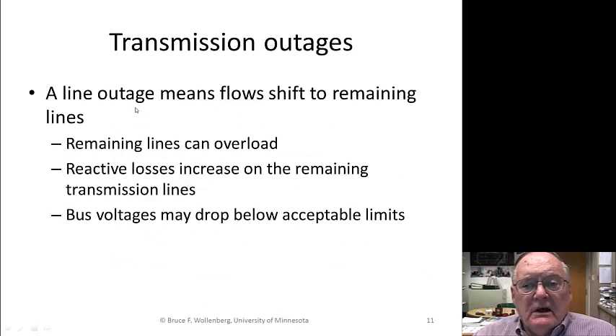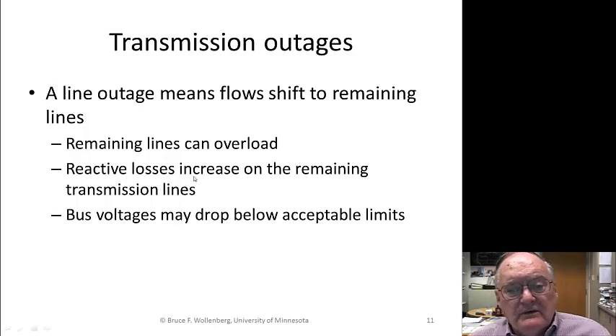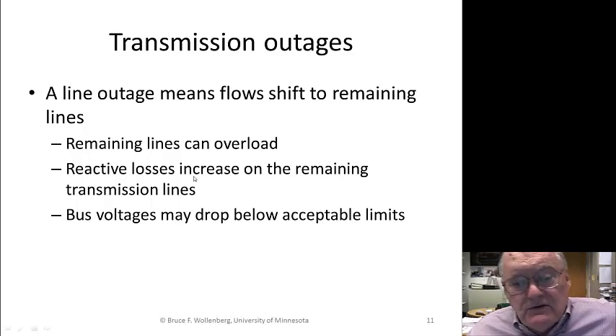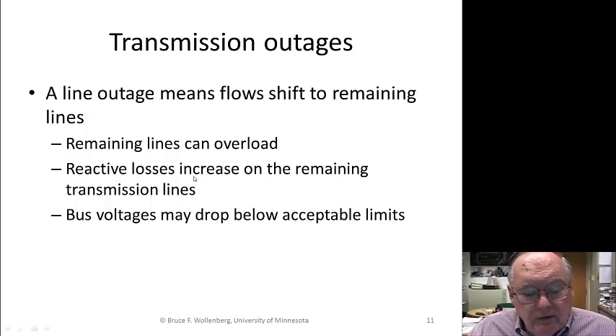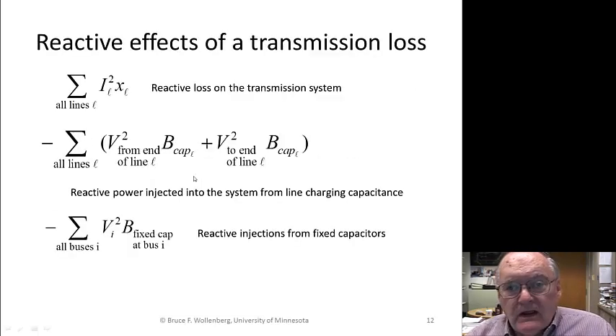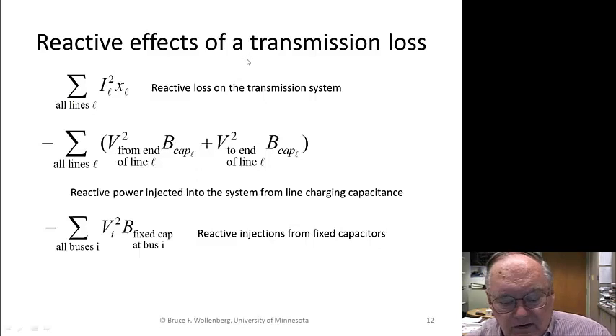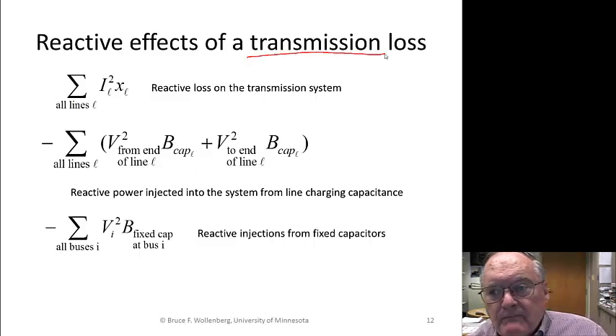Transmission outages. A line outage means flows shift to remaining lines. The remaining lines can overload. The reactive losses can increase on the remaining transmission lines, and bus voltages may drop below acceptable limits. Here's just to tell you some of the effects of a transmission loss. It says that for all lines, the line consumes reactive power as I squared X for the transmission line. So that's a loss.